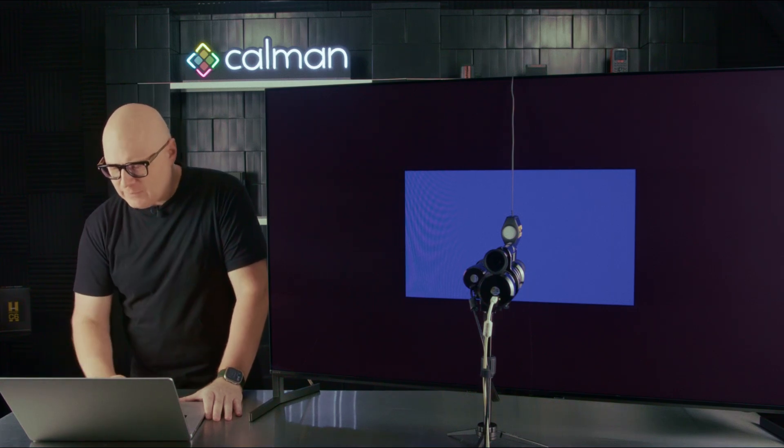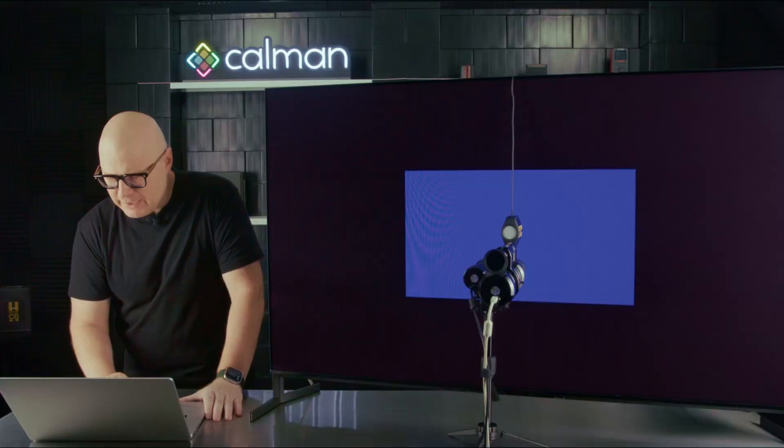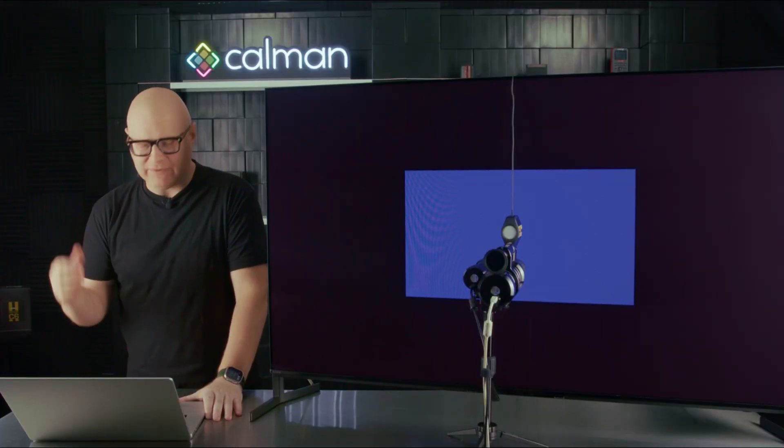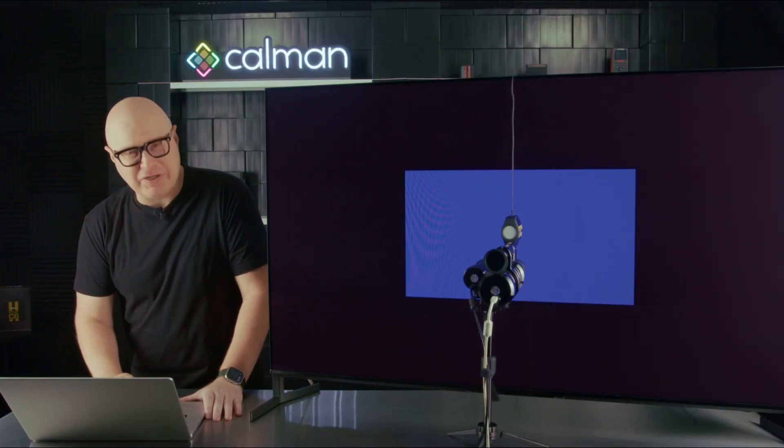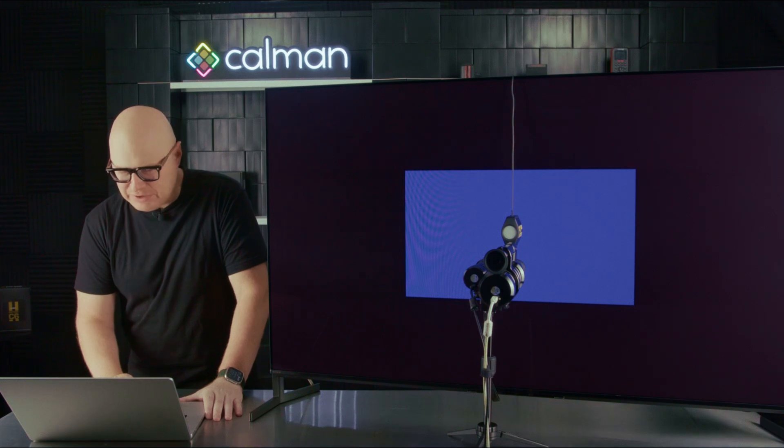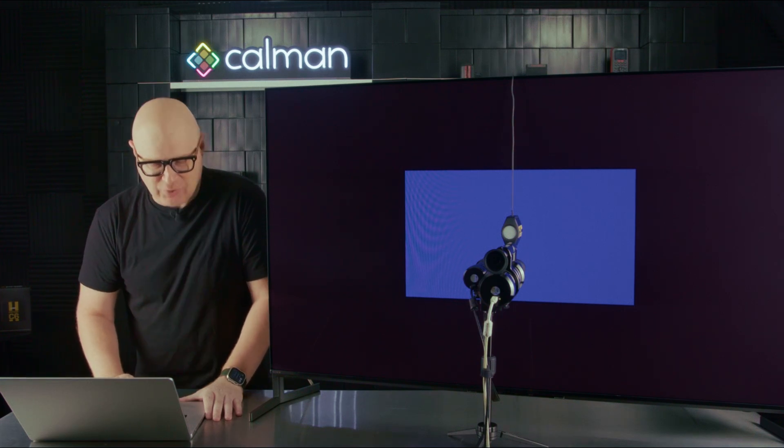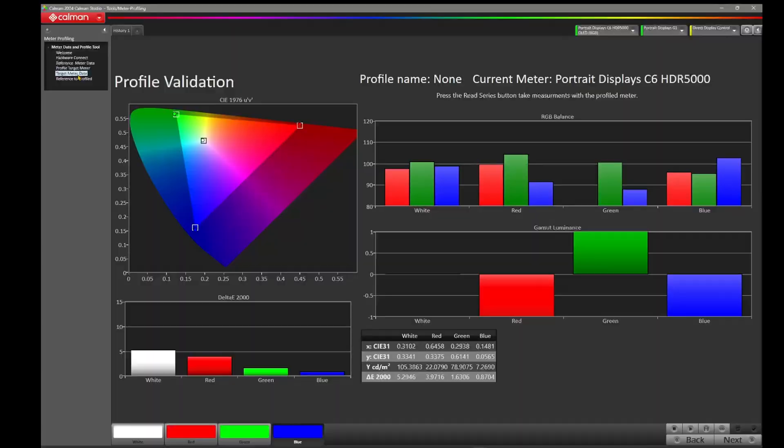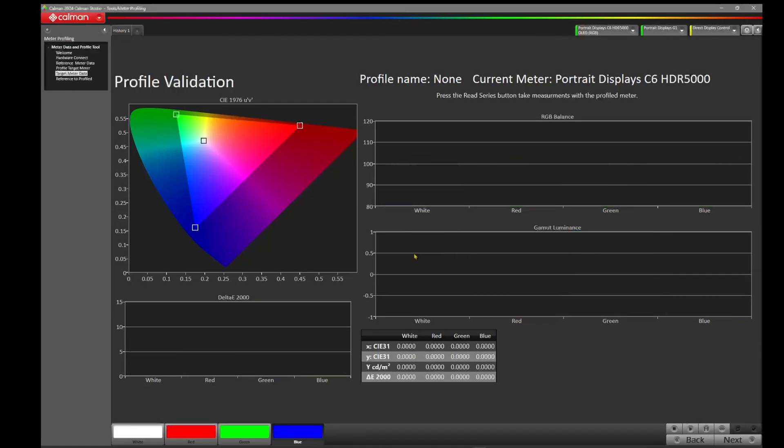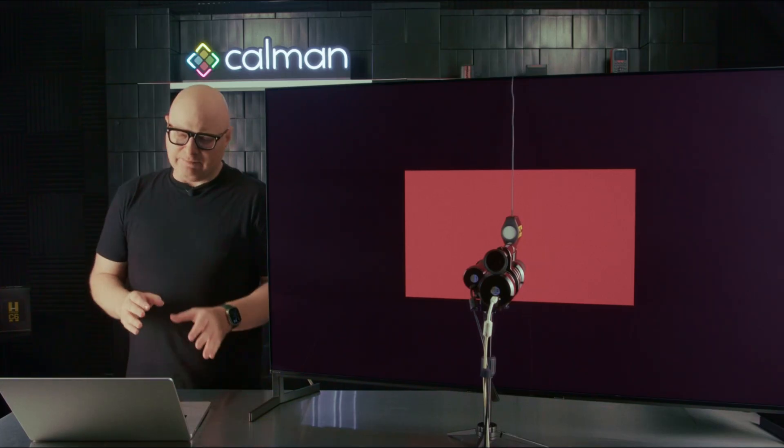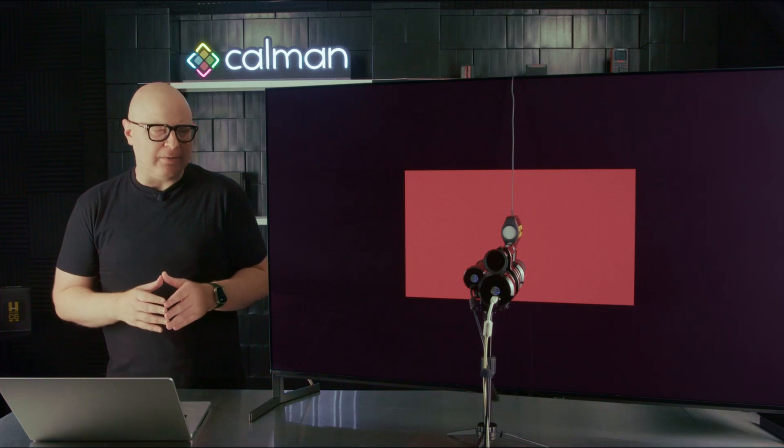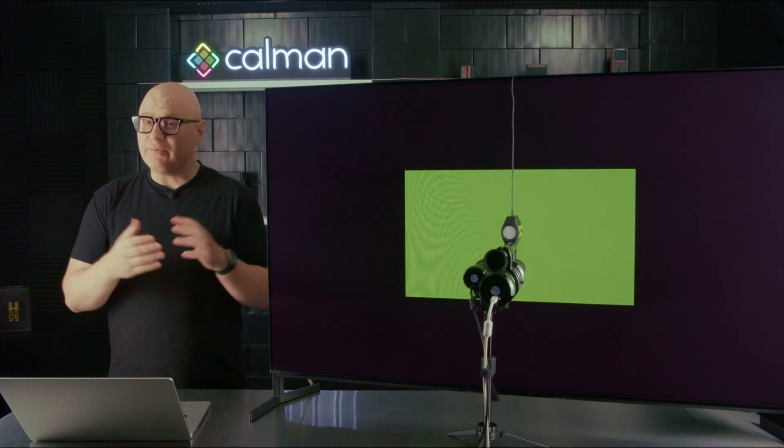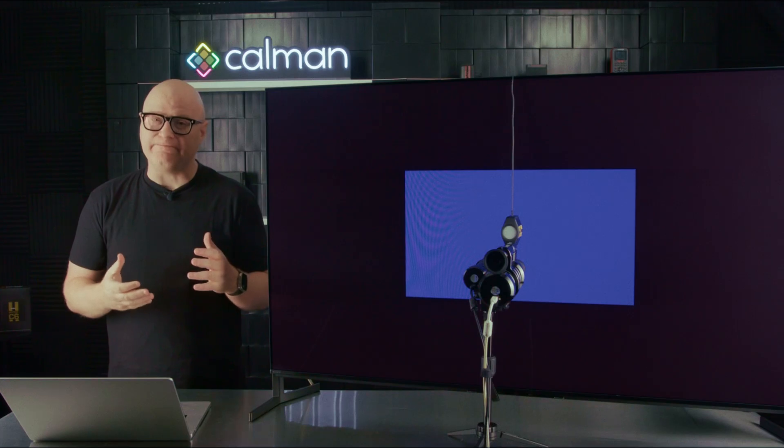Let's take a look at just another profile. That was the factory XYZ profile, but let's take a look at another profile that might be generic. Let's just go over to an OLED RGB profile that we have here. I actually don't know off the top of my head what display we were measuring when we made the generic OLED RGB profile, so this is going to be just as much of a surprise to me as it is you. We switch back to the target meter data page. I'm going to once again clear the tab data and hit read series.